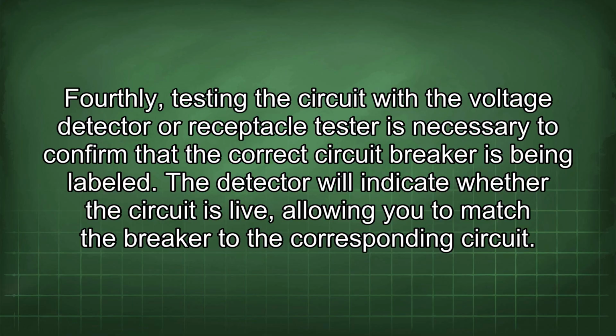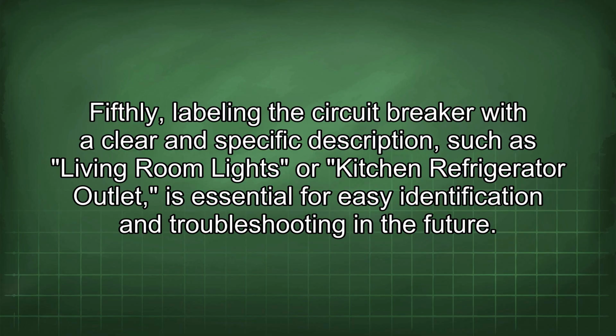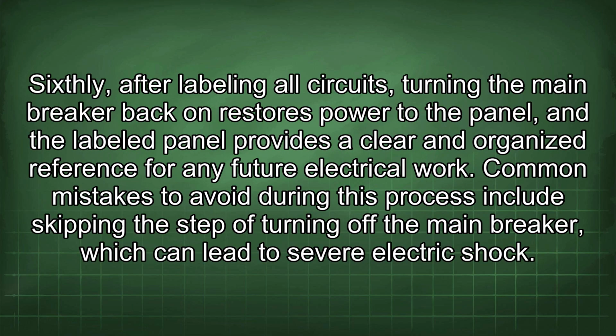Fourthly, testing the circuit with the voltage detector or receptacle tester is necessary to confirm that the correct circuit breaker is being labeled. The detector will indicate whether the circuit is live, allowing you to match the breaker to the corresponding circuit. Fifthly, labeling the circuit breaker with a clear and specific description, such as living room lights or kitchen refrigerator outlet, is essential for easy identification and troubleshooting in the future. Sixthly, after labeling all circuits, turning the main breaker back on restores power to the panel, and the labeled panel provides a clear and organized reference for any future electrical work.